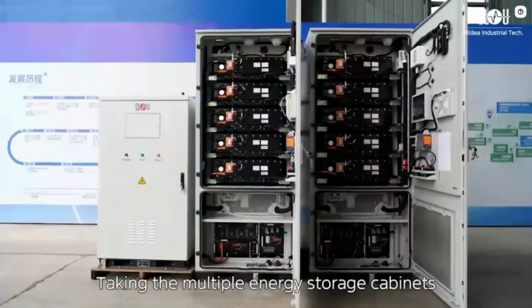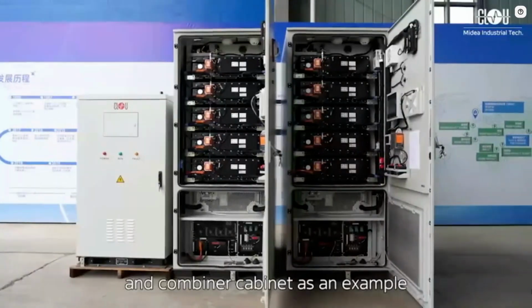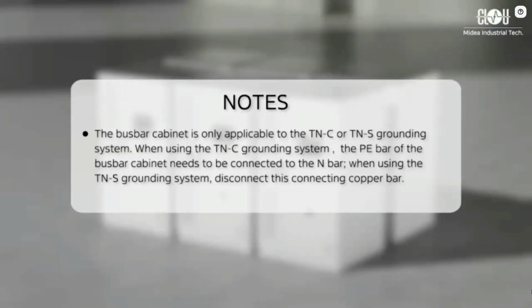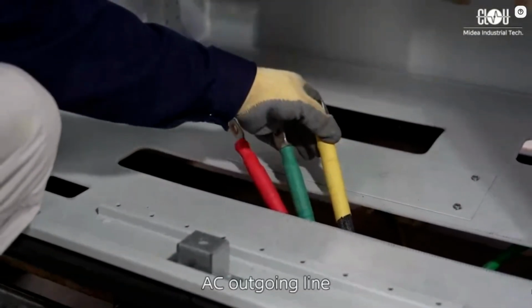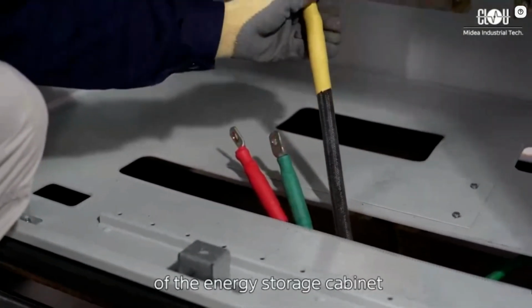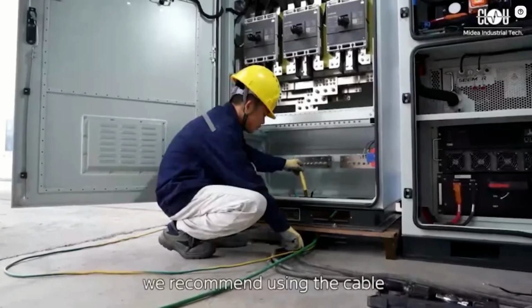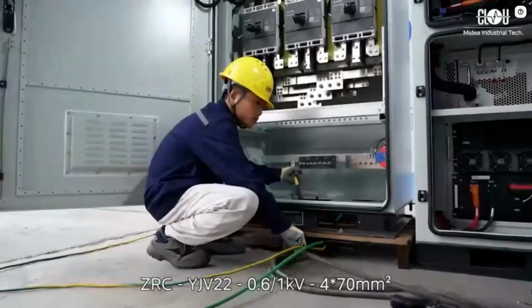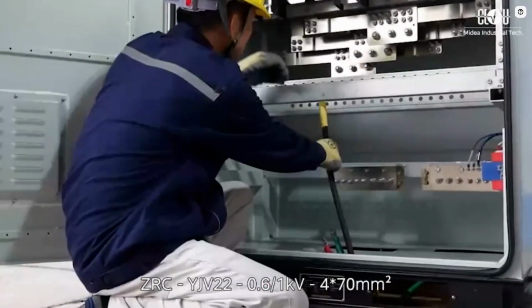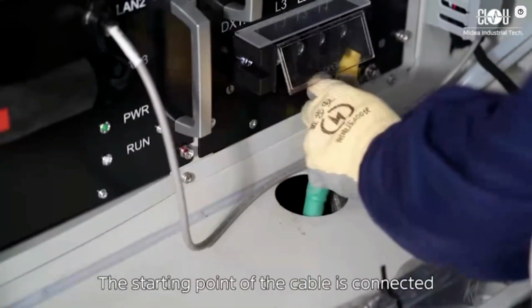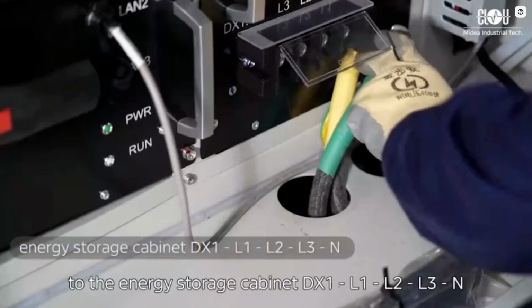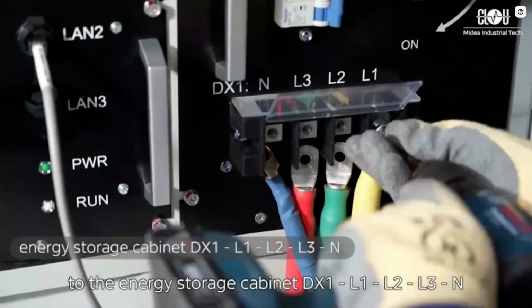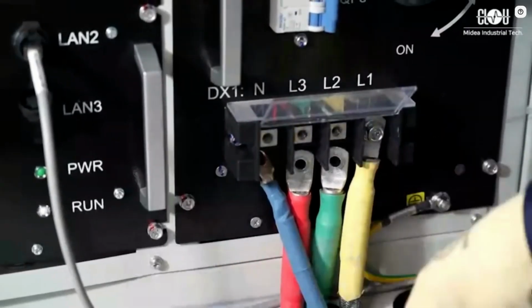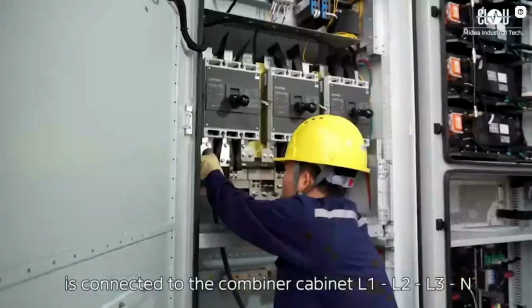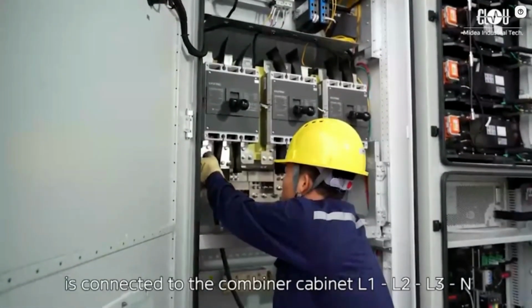Taking multiple energy storage cabinets and a combiner cabinet as an example: regarding the interface between the AC outgoing line of the energy storage cabinet and the combiner cabinet, we recommend using the cable ZRC YJV22 0.6/1 kV 4x70 square millimeters. The starting point of the cable is connected to the energy storage cabinet DX1, L1, L2, L3, N through the inlet hole, and the cable endpoint is connected to the combiner cabinet L1, L2, L3, N.